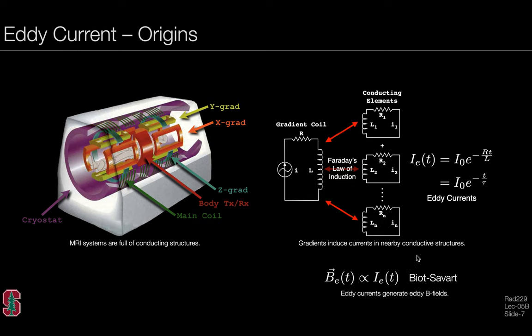According to the Biot-Savart law, these currents running through conducting structures inside the MR system generate eddy B-fields. These B-fields superpose with the designed fields — the gradient fields and the B0 field — and lead to problems with the imaging system.